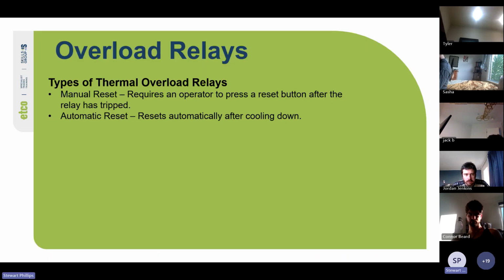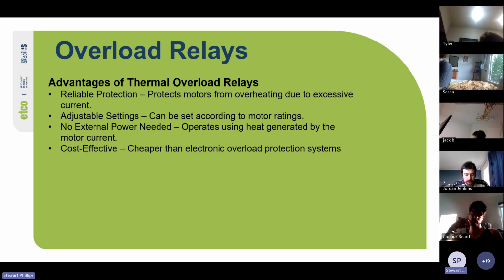Cool. So you've got your types of thermal overload relays. You've got your manual reset, which requires an operator to press a reset button after the relay is tripped. The automatic reset, which resets automatically after cooling down. And then obviously you've got your selectable ones, like the one we were just looking at. So the advantages of thermal overload relays: they're reliable protection. They protect motors from overheating due to excessive current. They're also good for phase loss, because if one phase drops out, it'll draw more current through the other two, so it will protect against that as well.